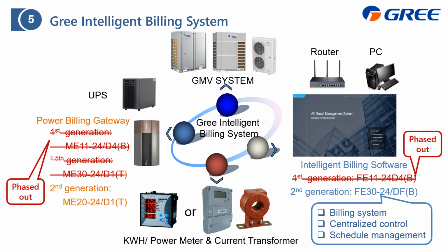Here is the material you should prepare. GMV system is of course. Then the power billing gateway, which is this one, the latest one, and it should be equipped with this UPS. The purpose of this one is just to record the data on the gateway when the GMV system is operating, because all the data is only stored here. And if it cannot store any data, then it cannot do the later calculation, right? And next is this power meter, and then the software which you install on the PC.